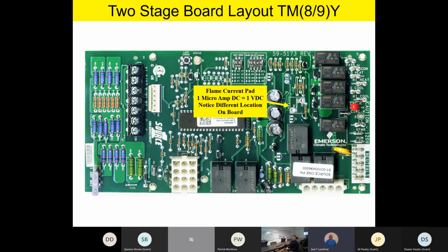So 1 volt DC on your DC voltmeter is equal to 1 microamp DC flame current. Unlike our competitors that make you take the little wire off and have a special meter and all that stuff, you don't have to do that anymore. You don't have to have a special flame current meter anymore. You can use just your standard voltmeter on DC volts, and then when you read between those contact points on the flame current pad, 1 volt DC is equal to 1 microamp flame current. So it's really simple and easy to read flame current now on the boards, and all of our Johnson Controls Champion products feature a flame current pad.